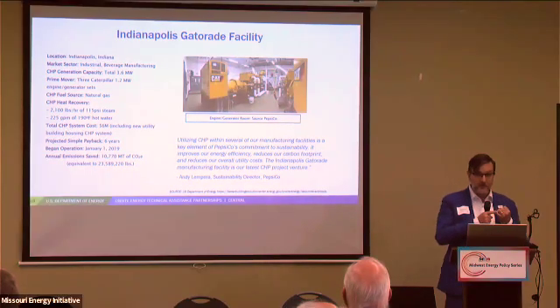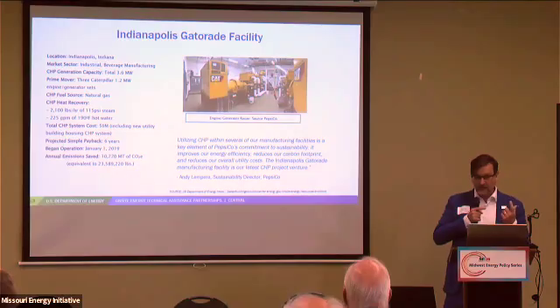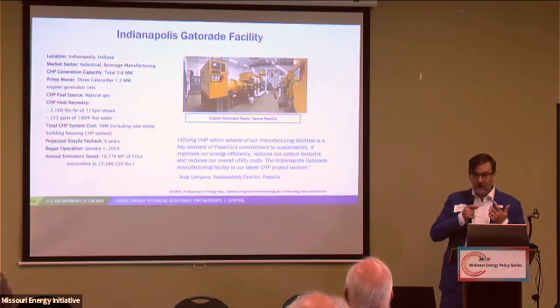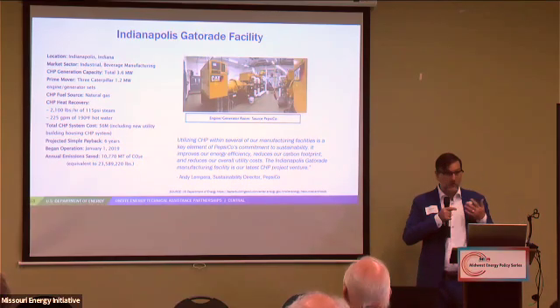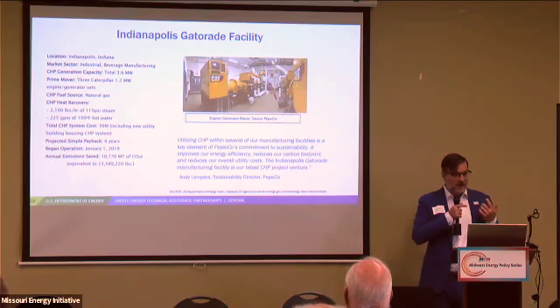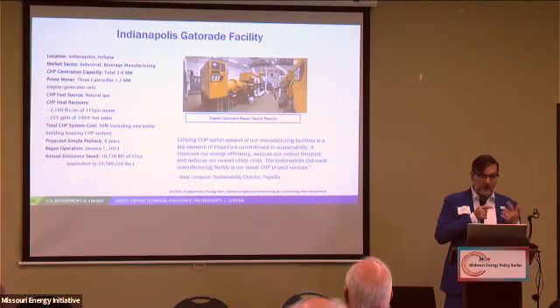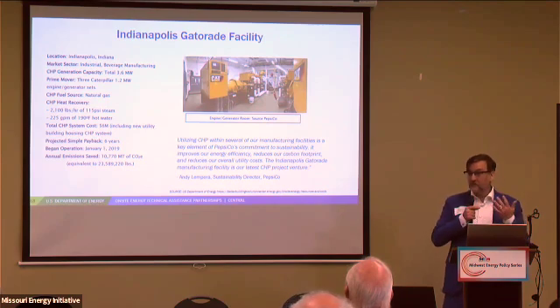These engines produce 2 types of thermal energy. They produce steam from the exhaust coming out the back, roughly 500 to 600 degrees Fahrenheit, making steam at 115 psi. They also take all the jacket water, the radiator system, and collect that to produce 225 gallons per minute of roughly 190 degree Fahrenheit hot water. So they take and use all the thermal energy these engines can provide.